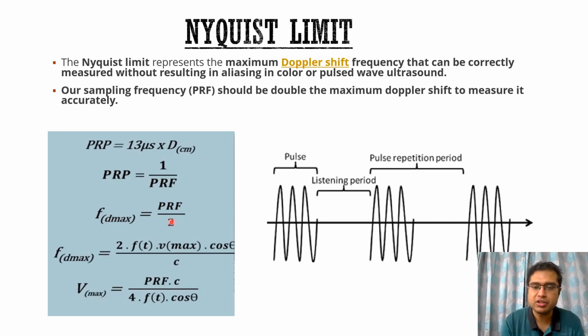So what exactly is pulse repetition frequency? This is the waveform that is seen in a pulse wave Doppler. We send a pulse and then we listen, and then we again send a pulse and then we listen. The time taken from the start of one pulse to the start of the next pulse is called the pulse repetition period. Pulse repetition frequency is inversely proportional to pulse repetition period. Pulse repetition period can be represented by 13 microseconds times d, that is the depth of that particular vessel. Substituting all this into the Doppler equation, we get this equation to calculate the maximum velocity in the vessel.